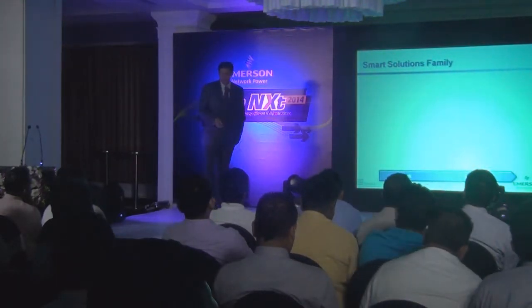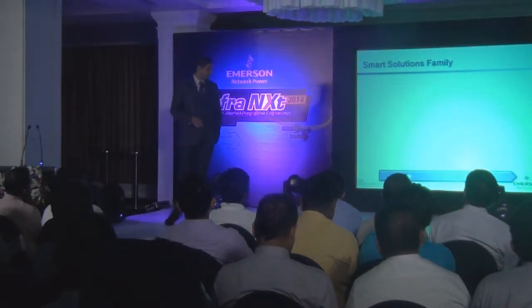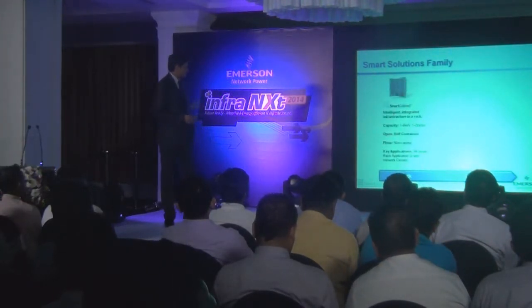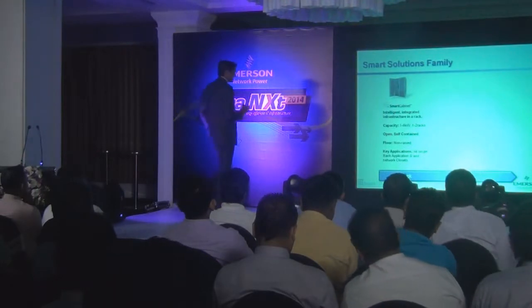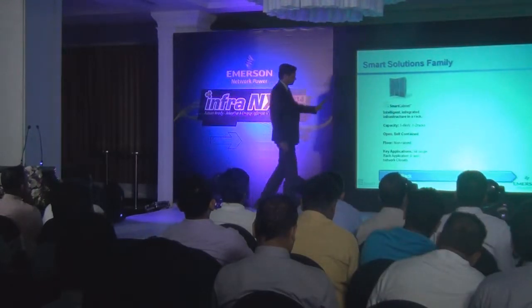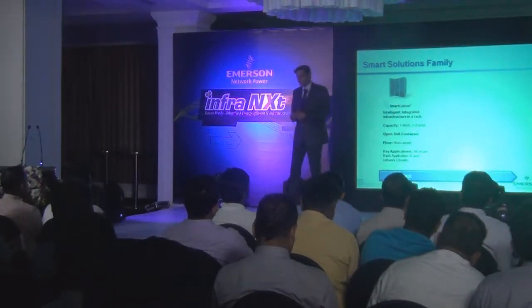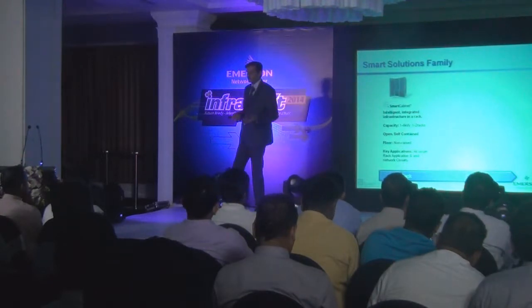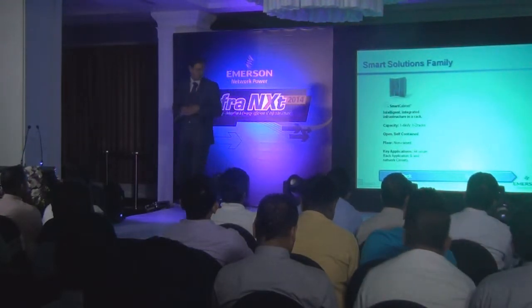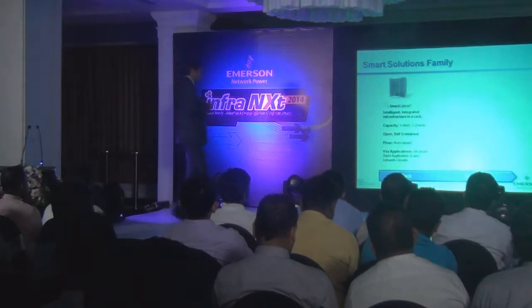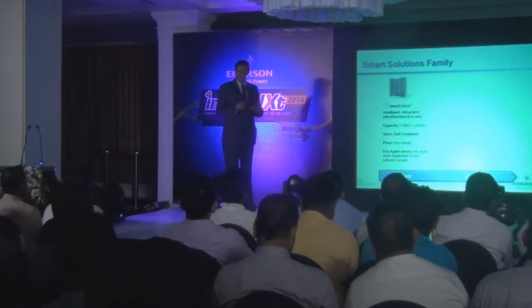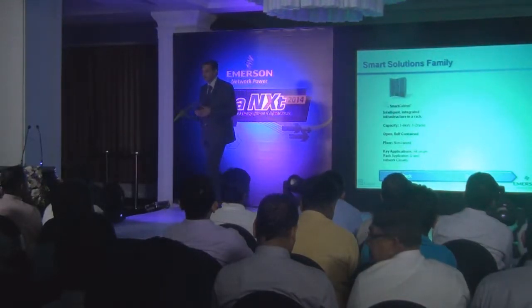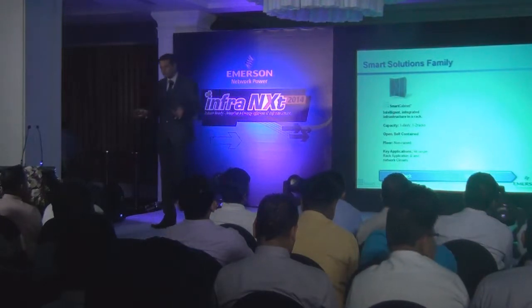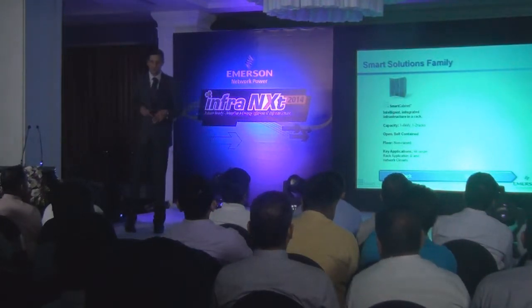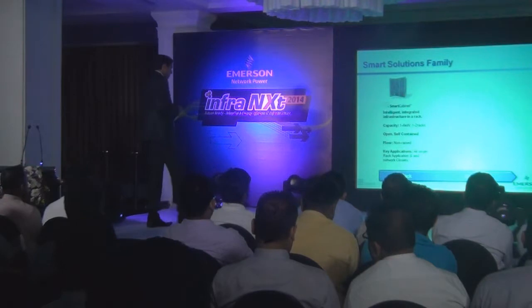So primarily I'm going to cover the smart cabinet and smart row. Smart cabinet is an intelligent integrated infrastructure in a rack, a single or 2 rack solution. If you have an IT load up to 6 kilowatts, we provide a smart cabinet solution. The cooling here is either open or self-contained, so we provide normal cooling as well as active cooling, both solutions are available.